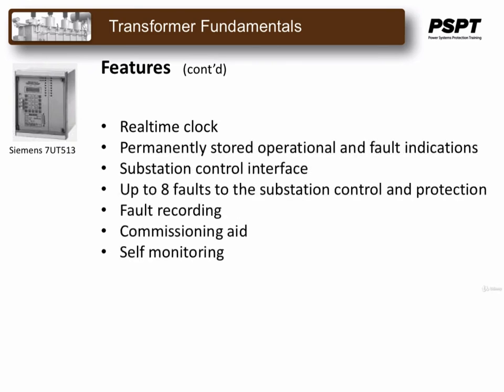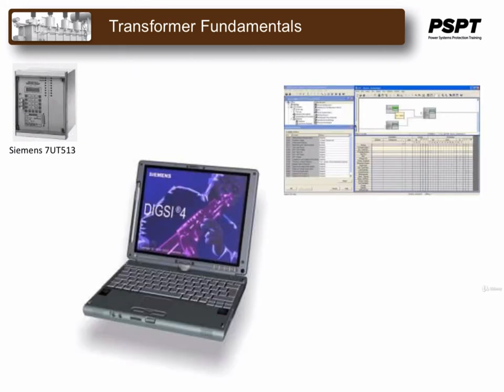It also features a real-time clock and permanently stored operational and fault indicators in the event of auxiliary voltage failure. Substation control interface has also a commissioning aid for setting up new installations, and it is self-monitoring for internal faults. The 7UT513 can be accessed using the DIGSI operating program on a compatible PC front connected to the relay, or the substation control interface can be a fiber optic interface or a standard substation control system interface. Alternatively, this can also be an isolated interface using RS-232C.